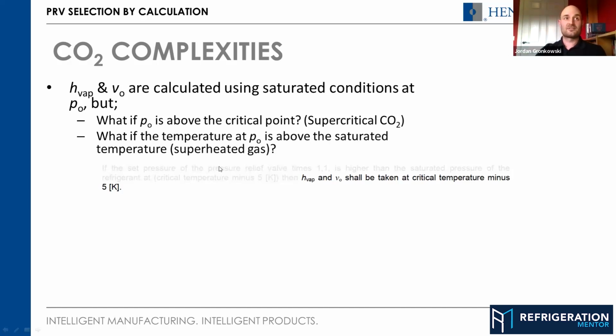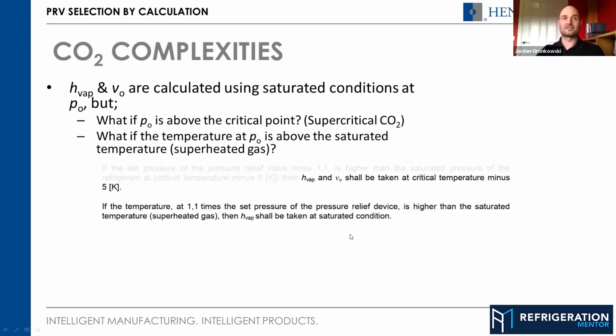What if the temperature is above the saturated temperature? So you've got superheated gas. Then again, the standard effectively says that if you have a superheated gas, then h_vap shall be taken at saturated conditions. So even though you're to the right of your saturated line, you take the values from the saturated line. You mentioned it there, Trevor, the risk of solid CO2 formation in the discharge of the PRV line.